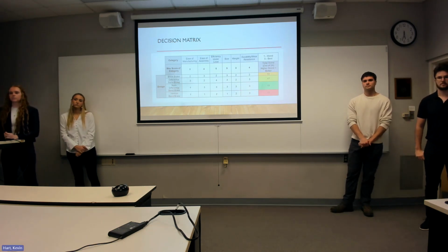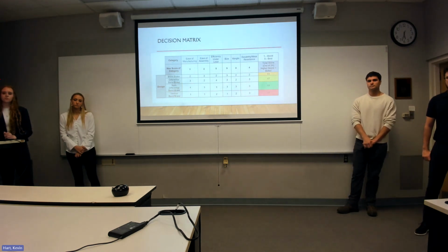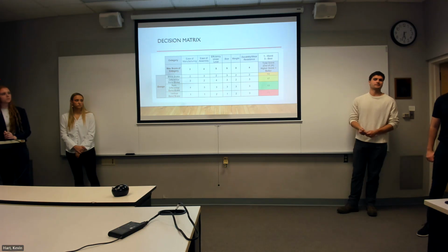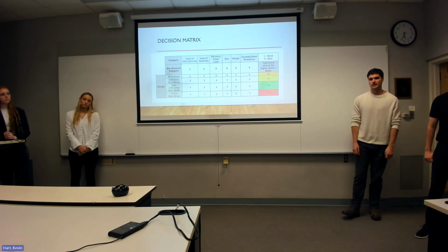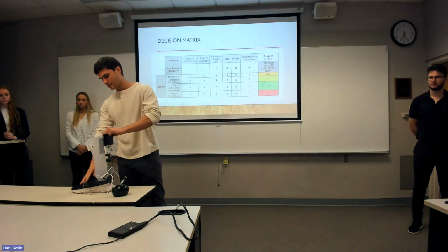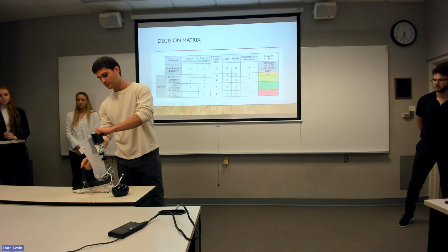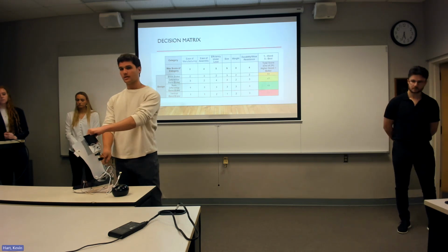Can you briefly explain how the solenoid works to help control the brake? From our understanding and brief talks about it, and what was in the prior report, once it hits... I guess I can show it right now. I believe there's a sensor here and then back here, and once it hits a certain angle, and I believe that's 50 something degrees, then it'll lock.